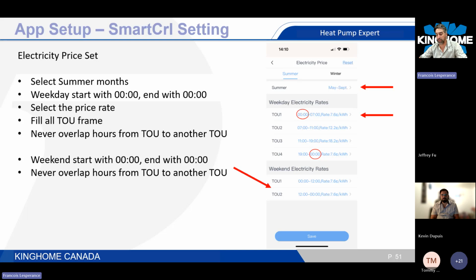Whenever you have to change between heat pump or gas furnace, okay? So basically, the algorithm, based on the COP of the system, will do all the calculation to make sure they start the cheapest utility, using electricity or gas. So during my time of use number 3, for example, if it's pretty cold outside, but not enough to bring my balance point to switch over, then the cloud can also set, okay, the gas is cheaper at that point, so gas will start right away. So this is a great advantage of using this thermostat because it will greatly help the customer to save money.